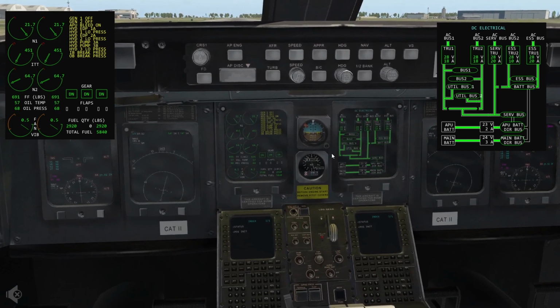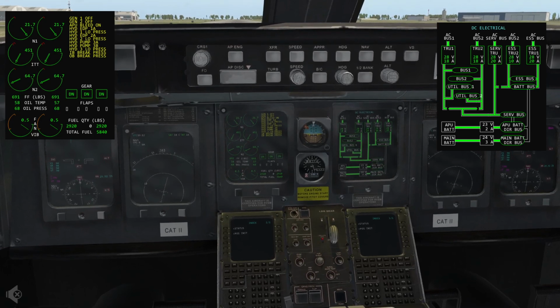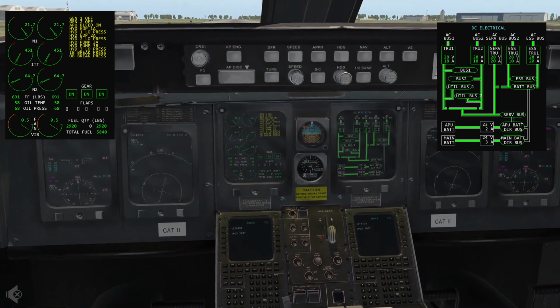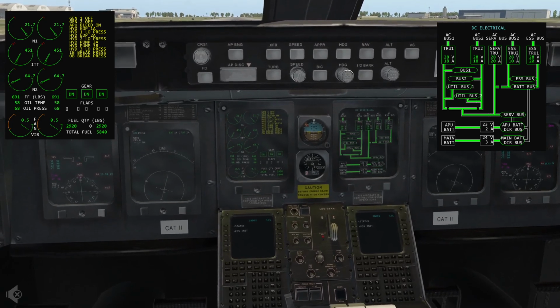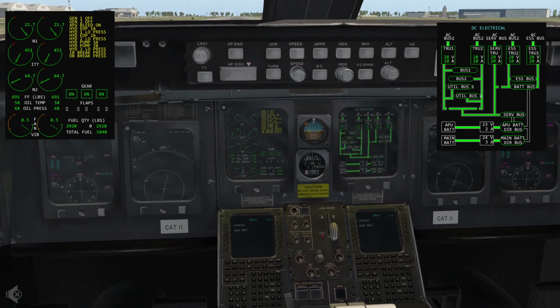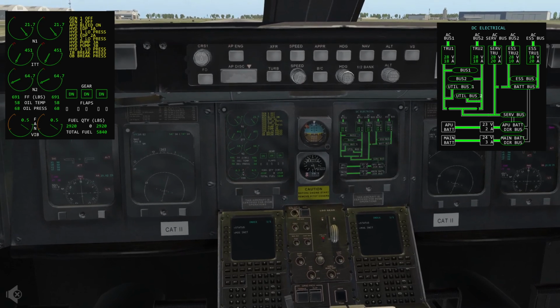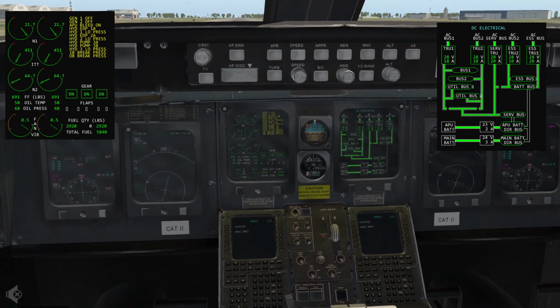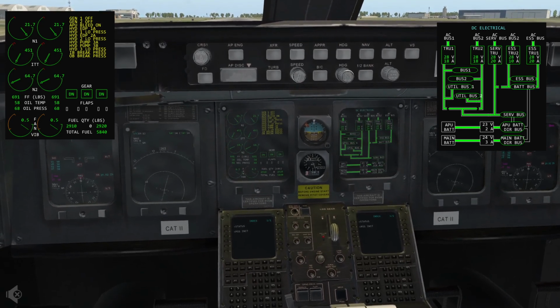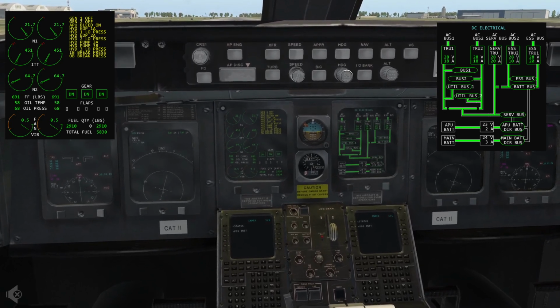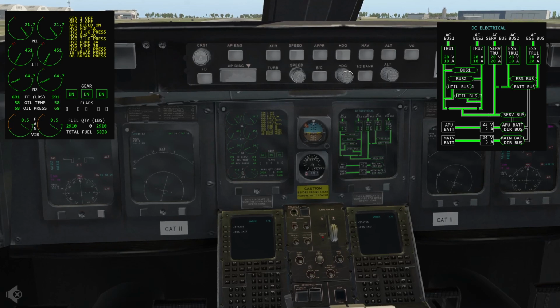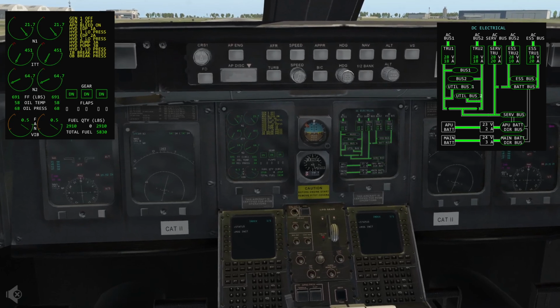How does the constant speed drive maintain a constant RPM? It's basically a hydromechanical unit that uses an integral oil system to drive the generator at a constant RPM. The constant speed drive is driven by the engine accessory gearbox, which turns at a variable speed based on the engine speed.